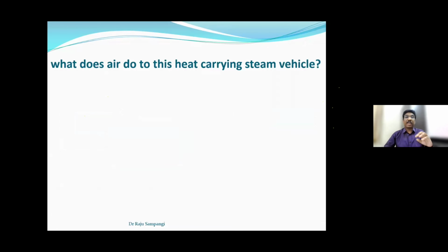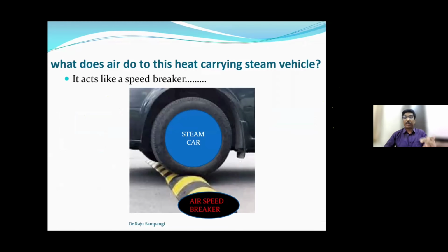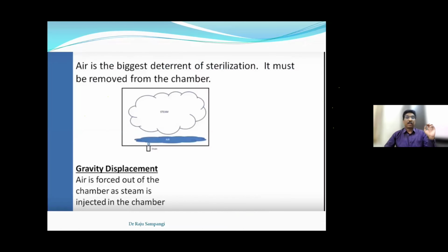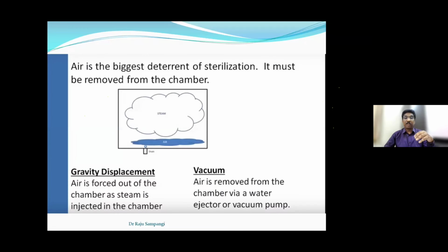So what does air do to this heat-carrying steam vehicle? It acts as a speed breaker. It doesn't allow the steam to contact the load. In a gravity displacement autoclave, the air is forced out of the chamber as the steam is getting injected, while in a Class B autoclave, it is actively removed via a pump.